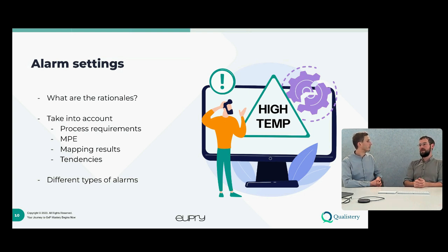And then you actually have to deduct that from your settings. So if you need to store something between 8.00 degrees and 2.00 degrees, you actually need to set your alarm settings at 2.5 degrees and 7.5 degrees. Taking that into account is quite crucial, specifically when we start talking about ULT freezers, where we'll often see a larger MPE of plus minus 1 degree, for example. So this is where the user requirement specification taps into the alarm setting.